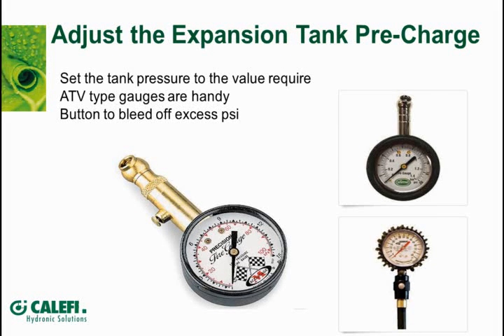So I would just find one of these little gauges. I actually bought this one right here at the auto parts store. What I like about this is it's a low pressure gauge. You can see it goes up to 15 pounds, so it's going to be more accurate at these lower fill pressures. If you've got a 60 or 100 pound air test gauge out in the glove compartment of your truck, it's really hard to read the difference between 11 or 12 or 15 pounds pressure on a high pressure gauge like that. So get one of these here.